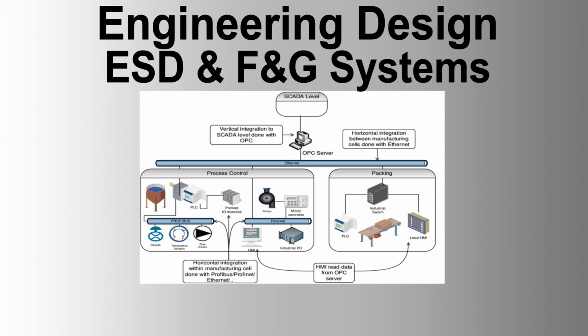4. Testing and commissioning. Comprehensive factory acceptance testing, FAT, and site acceptance testing, SAT, to ensure system functionality and compliance. Pre-commissioning and commissioning assistance, including loop checking and troubleshooting. Support during the startup phase to ensure smooth operation. 5. Documentation and training. Provision of detailed system documentation, including installation guides, wiring diagrams, and user manuals. Training programs for operators and maintenance personnel to ensure proper system operation and upkeep.